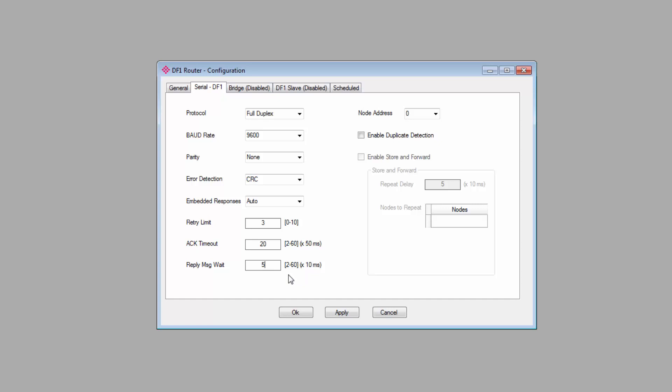The reply message wait is intended for situations where some older legacy controllers, if the response comes back too quickly, they'll miss it. So you can add a slight delay to responses to ensure that the controller is able to process it. I'll just leave it at 50 milliseconds.